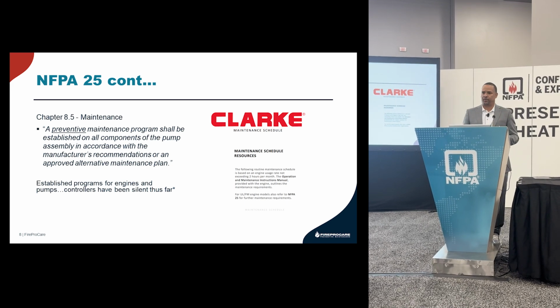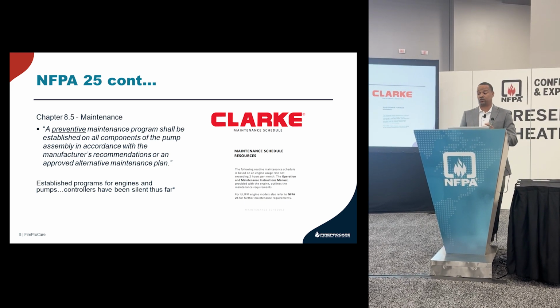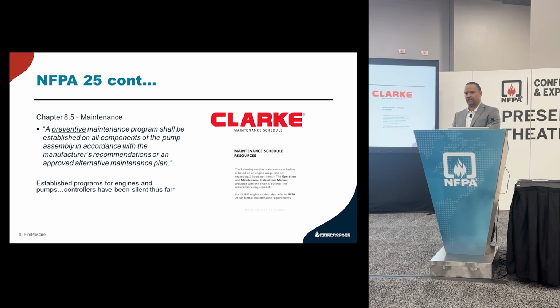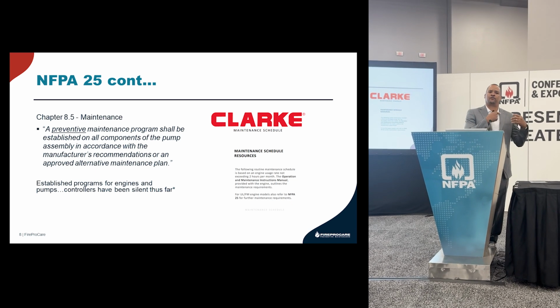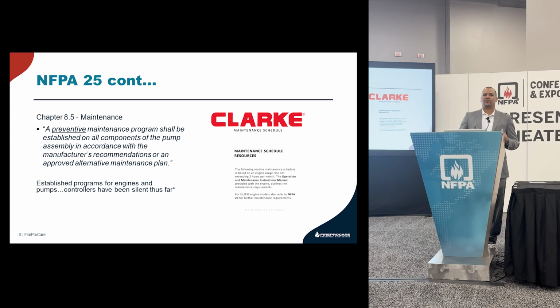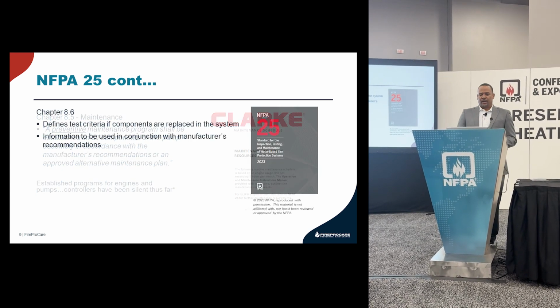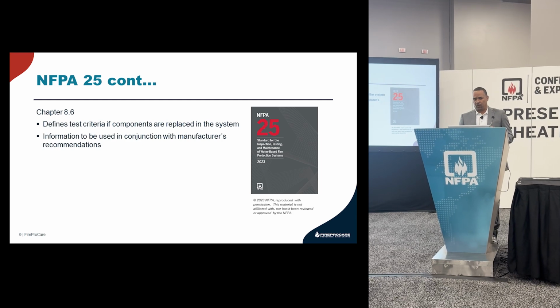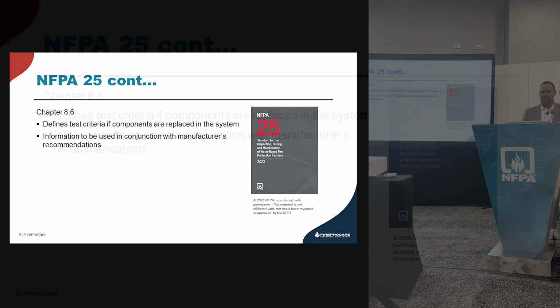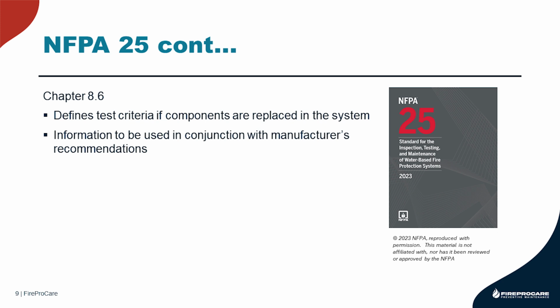When there's a problem in the pump room, everybody walks in there, they don't go straight to the pump or the engine, they go to the controller that's setting off the alarm. This is why you need to maintain your fire pump controller. So, NFPA 25 and section 8.6 is very general in nature. It talks about certain things like replacing certain parts and what you should do after you replace those parts.